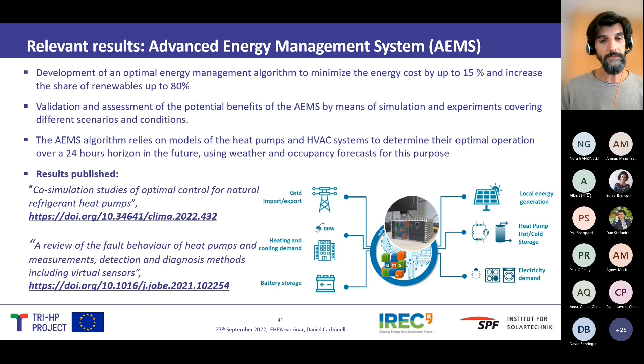So what we're doing now, since we're at the end phase of the project—we started from materials, went to heat exchangers, then heat pumps, and now we go to systems. The way to test the systems is what we call hardware-in-the-loop dynamic testing. It's a system test where we test consecutively for several days. We do it over 6 days, where these 6 days represent the whole year. They are selected so that when we test the system continuously for 6 days, we know the efficiency of the system over a year, and these days represent different times of the season.